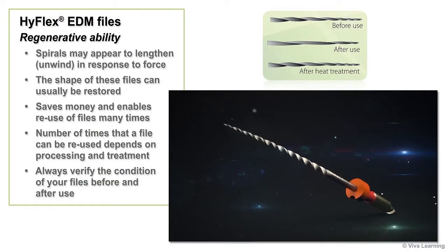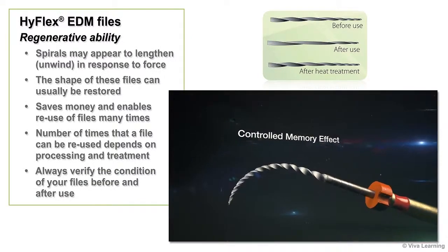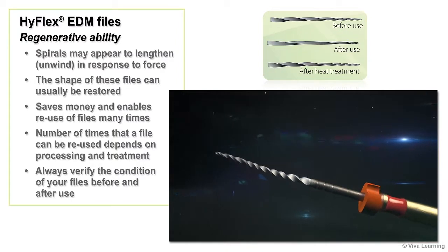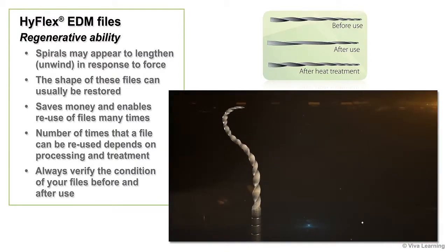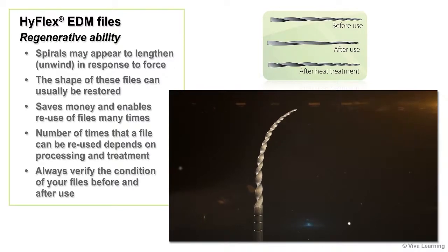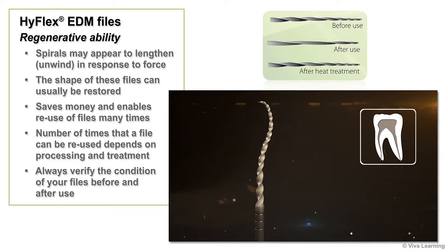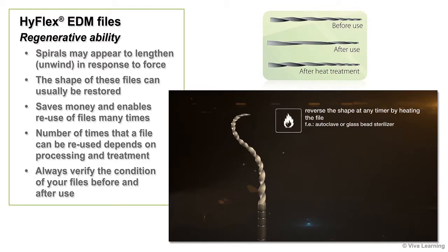As you use the HyFlex EDM files, you'll see that their spirals may appear to lengthen or unwind in response to force. But unlike other commonly available NITI instruments, the shape of these files can usually be restored. Provided the spirals do not wind in the opposite direction during use, they will regain their original shape during normal autoclaving or when a glass bead sterilizer is used for 10 seconds.